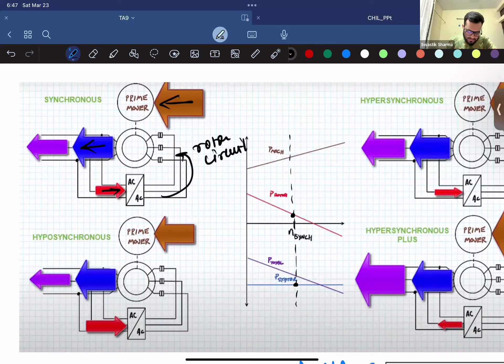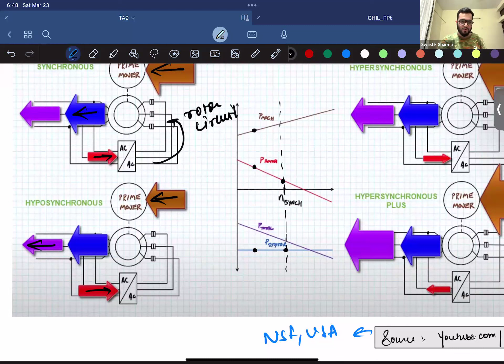Since the mechanical power is less, the rotor power needed would be more, so your rotor is taking power from the output of your stator. If it's at a constant speed, the stator power taken would be more, and since this is more, the total power output would be less, since you are taking some part of that power out to control how your rotor is behaving at a hyposynchronous speed, because you want to maintain that synchronous frequency. In the hypersynchronous speed, your prime mover is behaving very fast, injecting a lot of power. So you are working in this stage, let's say this stage.